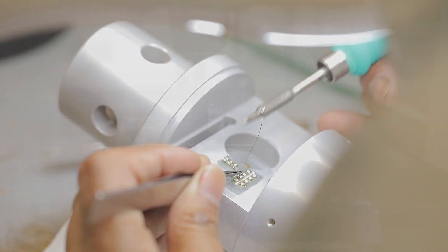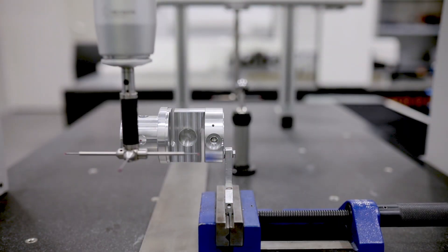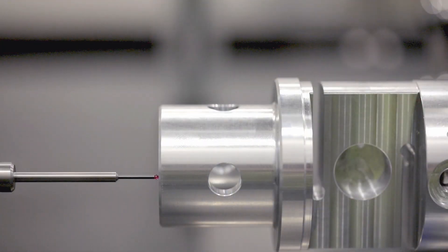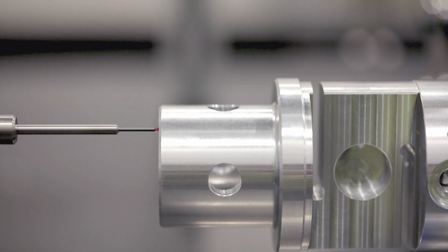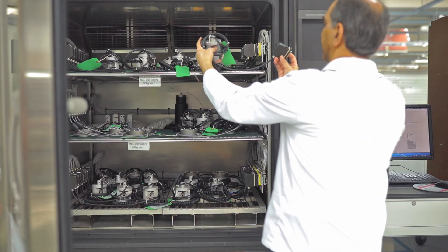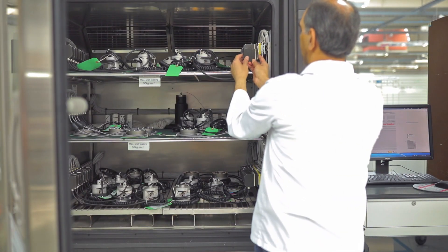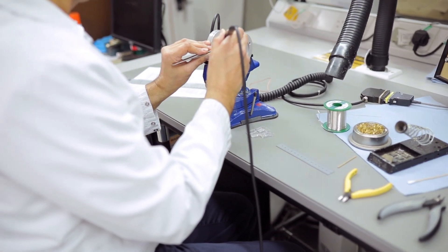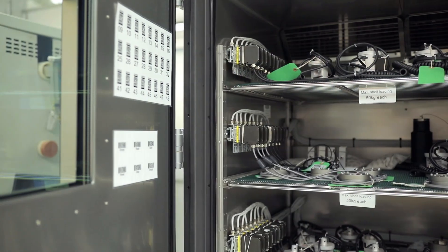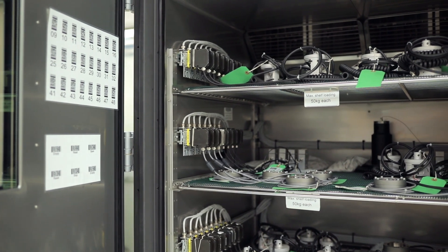All Instron load cells are subjected to a thorough test and verification procedure including temperature compensation. Our load cells are tested in our ovens and then adjusted as necessary. Afterwards, the load cells are then retested in the ovens to ensure compliance with our specifications.